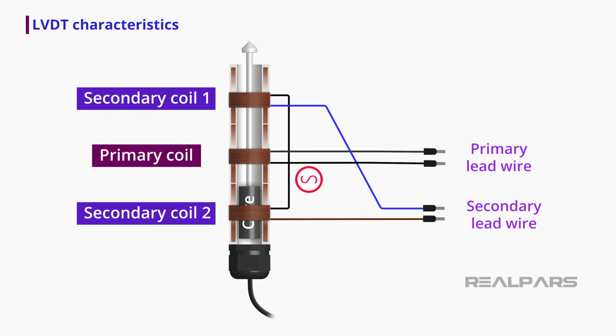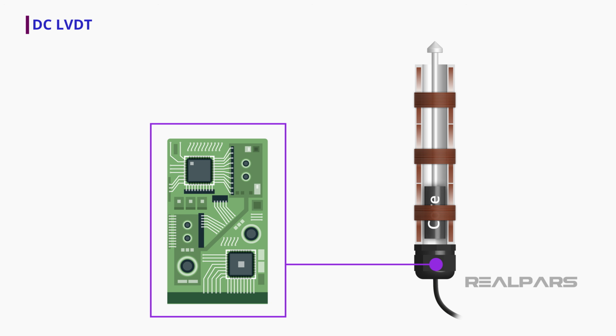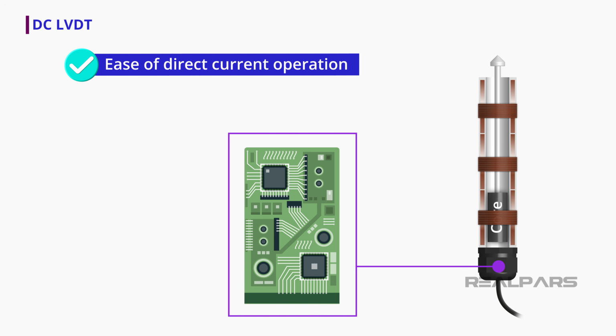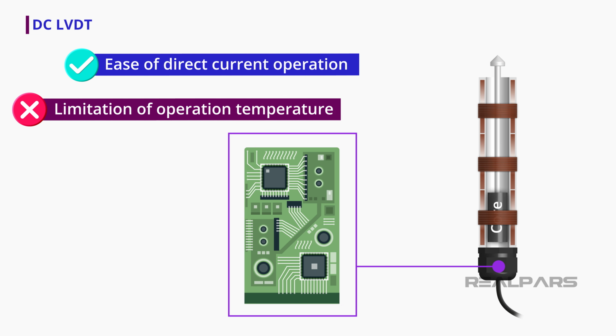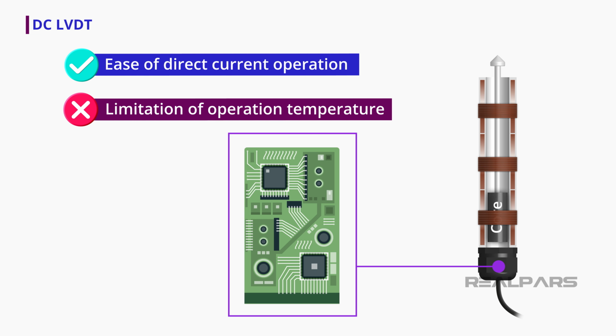When initially introduced, all LVDT position sensors were operated by strictly alternating current. Today's technology, however, allows for signal conditioning, or in other words, signal manipulation in a way that prepares it for the next processing phase, to be done inside the sensor's housing. The ease of direct current operation can be applied, maintaining all desirable characteristics of the alternating current LVDT. However, the electronic materials in the signal conditioning module bring limitations to the DC-operated LVDTs, such as the temperatures at which they can operate.